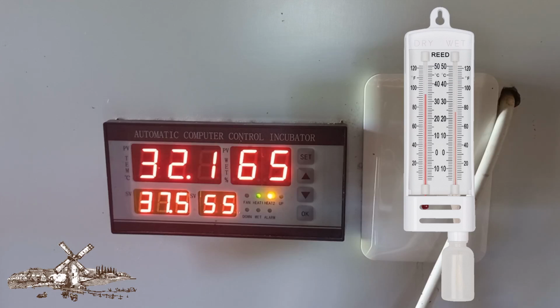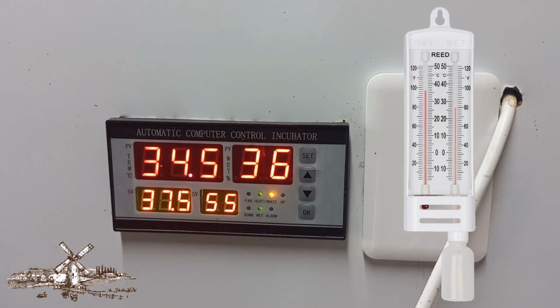So there you can see my controller is programmed for 37.5 degrees. And so whether my controller is accurate or not, my controller will heat the machine up to what it believes to be 37.5. Now, what I would hope is that my controller's dry temperature, the 37.5, would in fact match my dry thermometer on the right side. Because as I said to you, I can accept the dry bulb thermometer to be correct. And so if my controller shows me anything different to what my dry bulb thermometer does, then it means my temperature controller's temperature measurement is wrong, and I need to then adjust my measurement on my dry controller so that it matches the dry thermometer, my alcohol thermometer. Now, what you're going to see happen here is my alcohol thermometer settled on 40 degrees Celsius.